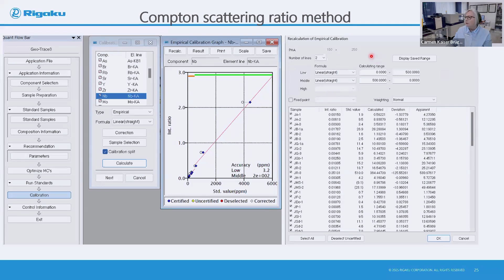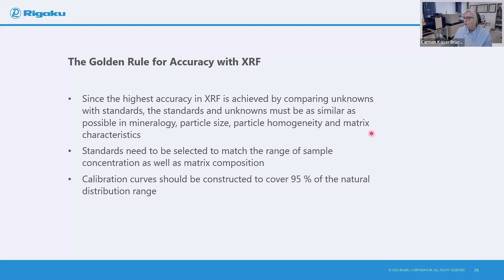So the golden rule for accuracy with XRF is that the highest accuracy can be achieved by comparing the unknowns with the standards with as similar a mineralogy, particle size, and particle homogeneity as the matrix characteristics. So the standards that we use need to match the range of the sample concentration as well as the matrix composition. Our aim is to cover at least 95% of the natural distribution range. This is a very important part that we often forget.